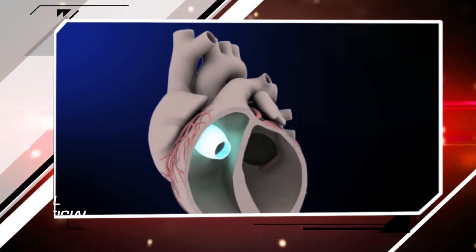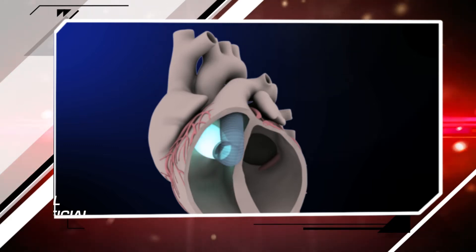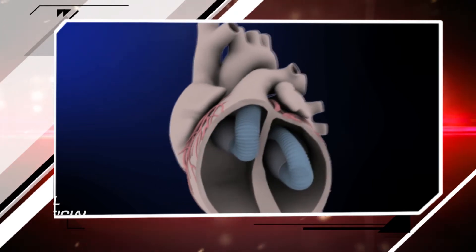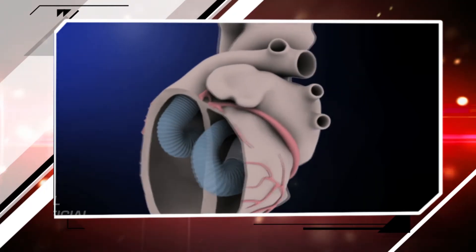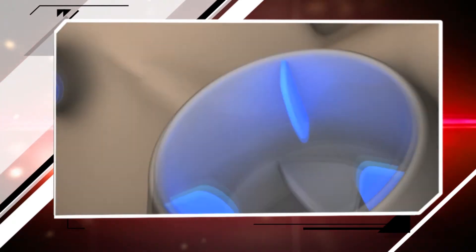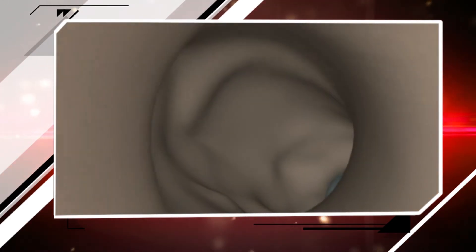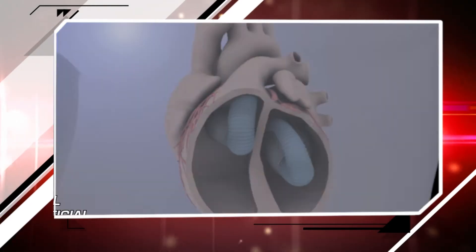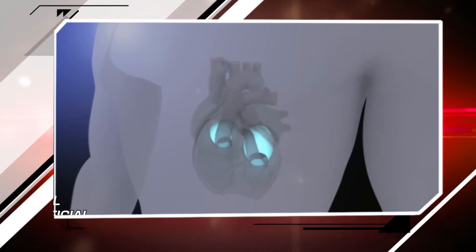This condition is very important for cerebrovascular accidents such as stroke. A specially designed motor requires quite little energy to operate and thus provides a longer battery life. The energy of the system will be provided through wireless energy transfer, which is achieved by transferring three phases of AC current simultaneously. The device uses three internal receiver coils and three external transmitter coils worn around the chest in the same plane.